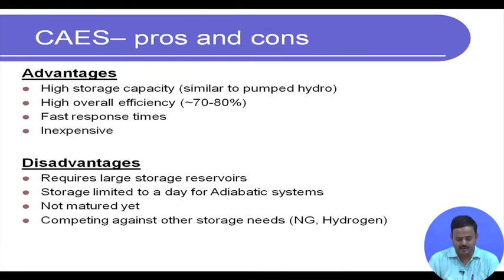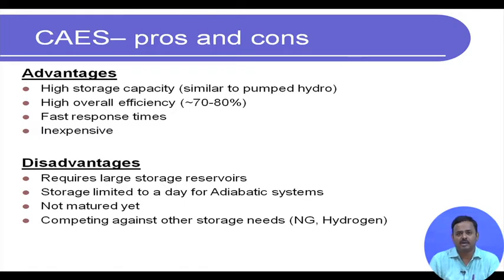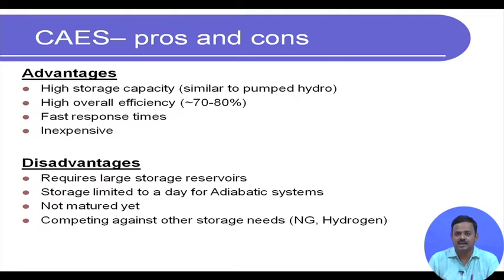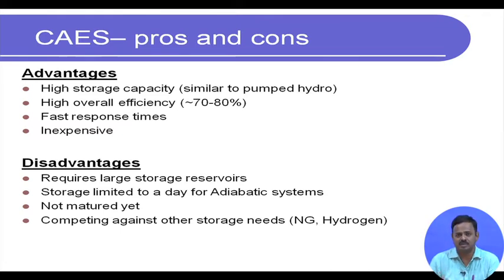Advantages of CAES: it can store a large amount of energy — high storage capacity similar to pumped hydro. Overall efficiency can be quite high, 70–80%. Response times are relatively fast, and it is inexpensive as long as you have the salt mine. Disadvantages: large storage reservoirs are not abundantly available across the world. For adiabatic systems — where no additional combustion energy is needed — storage is limited.